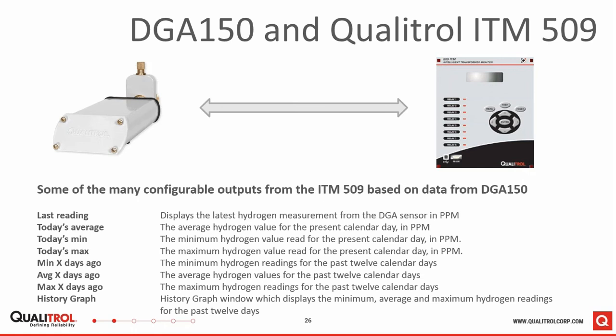Rate of change is another thing that we can calculate in these products, and as a matter of fact, for those that are involved with IEEE C57.104, IEEE is soon to release an updated standard that will include rate of change standards as well. But as Donald mentioned, IEC already has some guidelines on rate of change. And so if you can advance the slide, Donald.